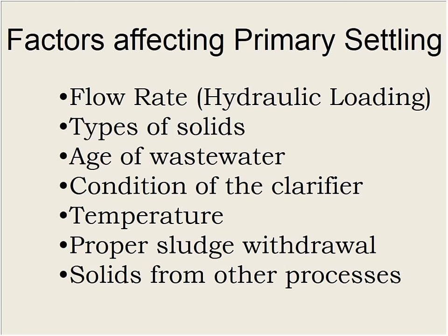Well, things that we're considering is our flow rate. Again, we want to run within certain ranges, so if we've got a lot of water coming in because of rain or what have you, we need more clarifiers. We've got a certain rate at which we want to run these in terms of hydraulic loading. The type of solids that are coming in, old sludge doesn't settle as well, the age of the wastewater, condition of your clarifier, obviously temperature is going to affect it.